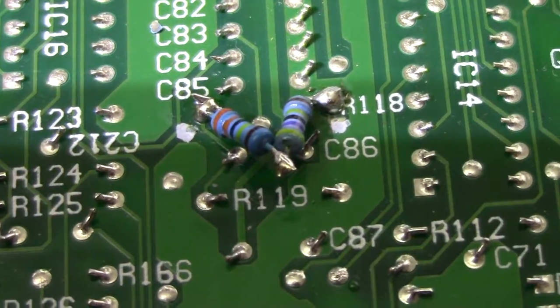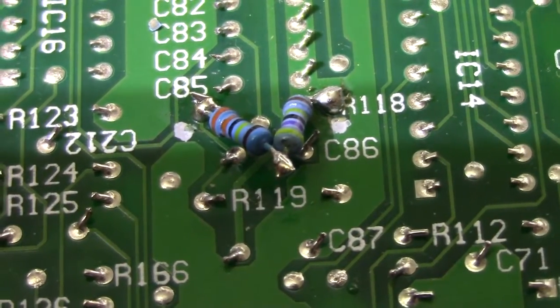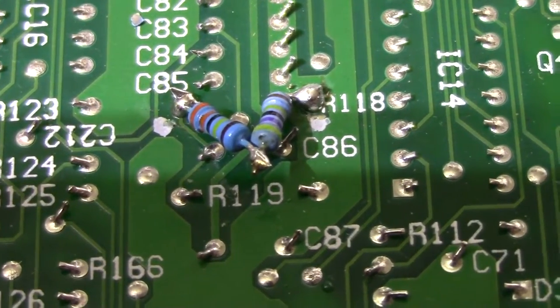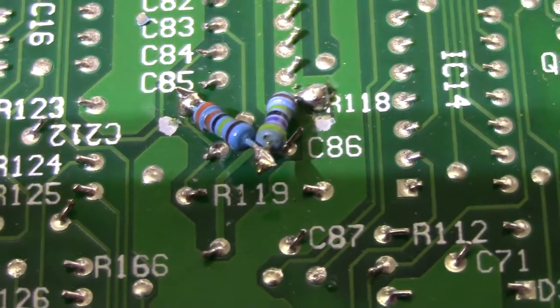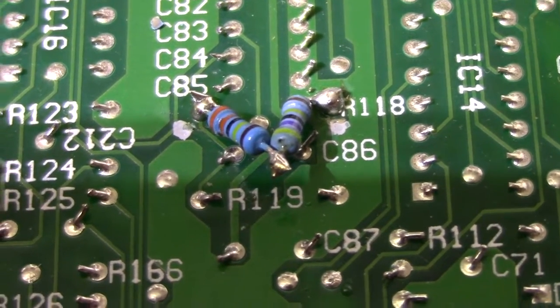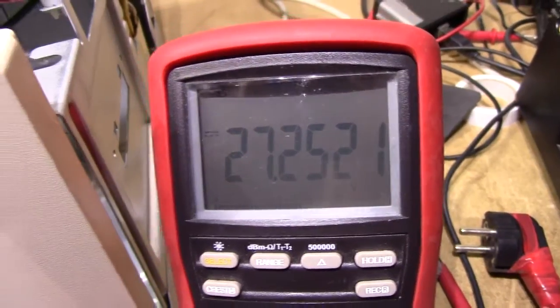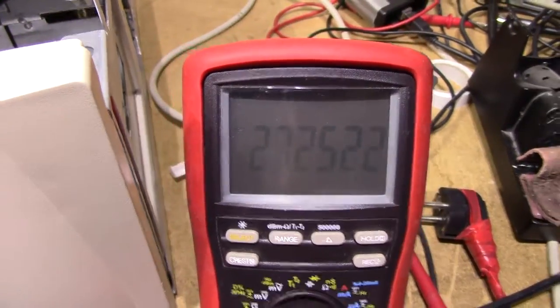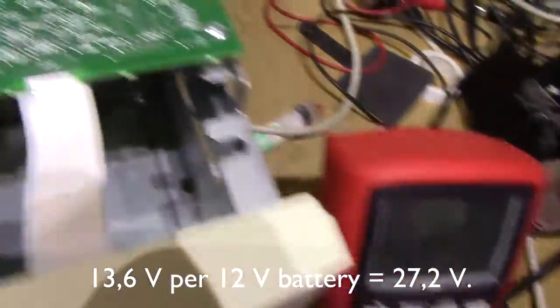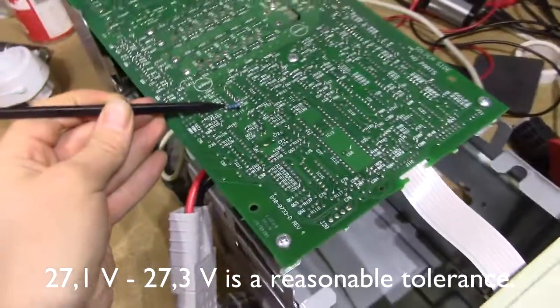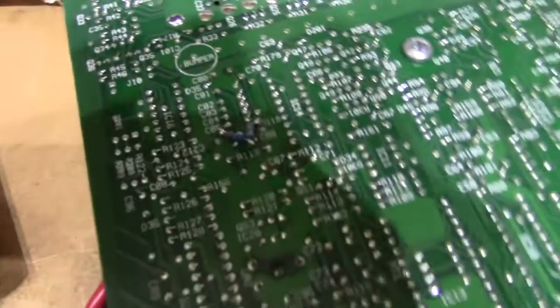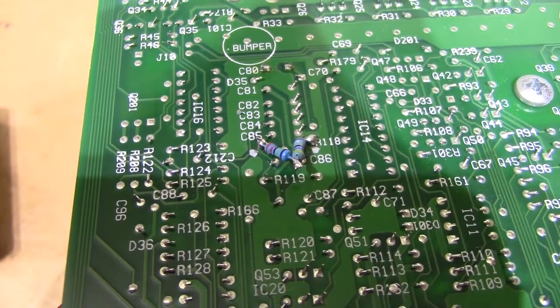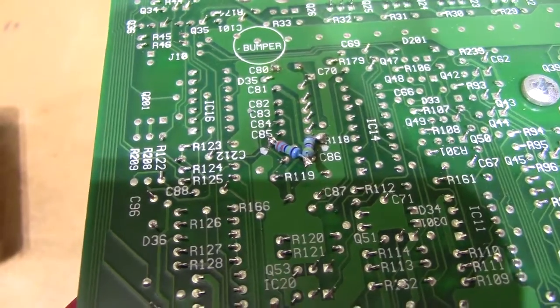Also, as a final ending note, if you want to change the charging voltage on these units, you can't do it through software. You need to install a bypass resistor across R118. I've used an 8 megaohm resistor right here, which gives me a charging voltage of 27.25 volts, which is about 13.6 something volts per battery. Which is okay, I usually shoot for 13.6. And that resistor is right there, right beside IC14, which is the charge controller IC. Which I also believe to be APC custom.